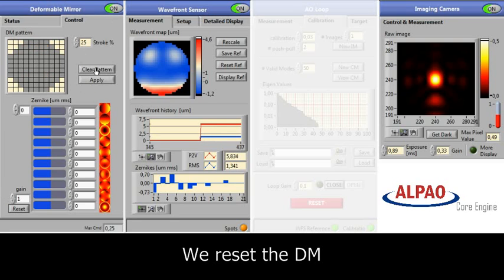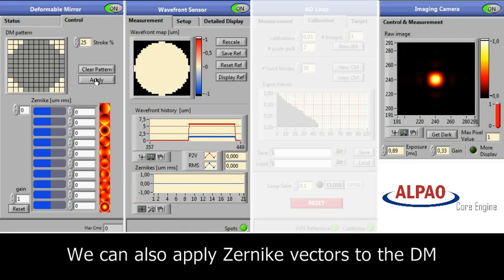To reset the deformable mirror, we click clear pattern, and on the wavefront sensor we can verify that the mirror is now flat.